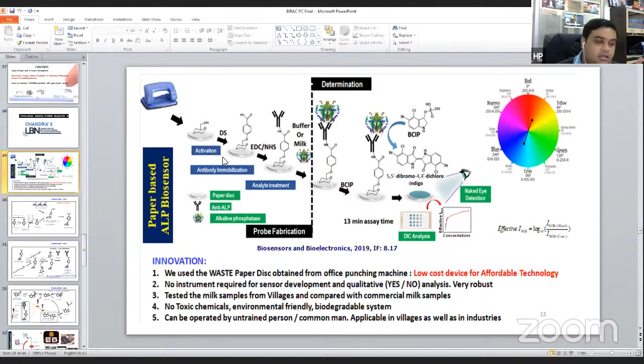The sensitivity is very good because we calibrated the system after a lot of optimization of reaction conditions, so it works very well in the range where ALP is naturally present in milk. When you do pasteurization, the ALP is denatured because it is an enzyme, but its denaturation temperature is quite high. That is why it has been used as a marker for pasteurization. In any milk industry, like Mother Dairy or Amul, they use the ALP system, not ours, to check pasteurization. So in terms of sensitivity, it is highly sensitive, and that's not a problem. The dynamic range is also very wide.